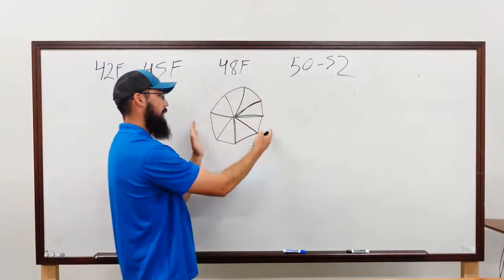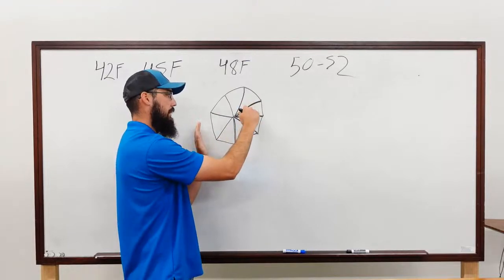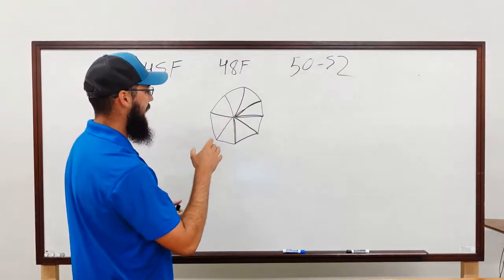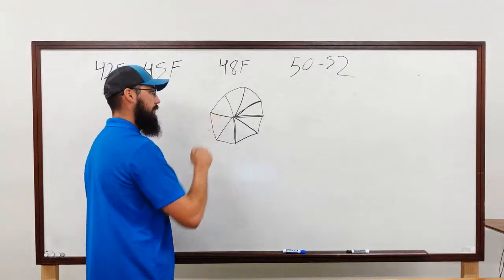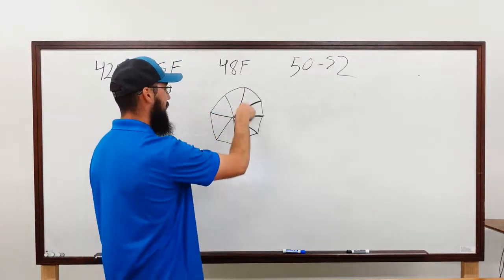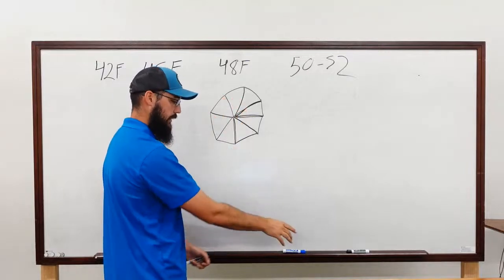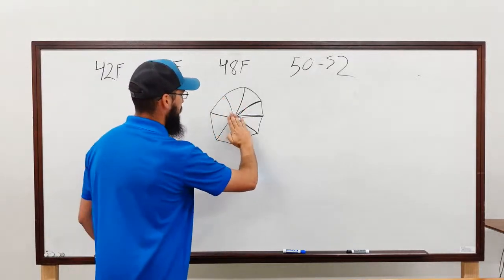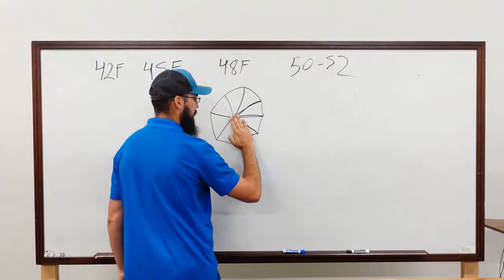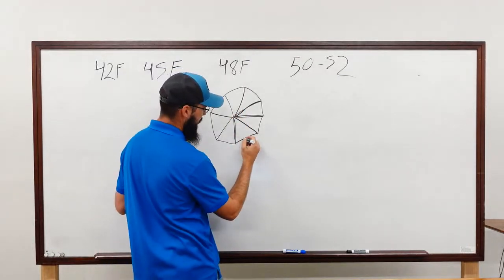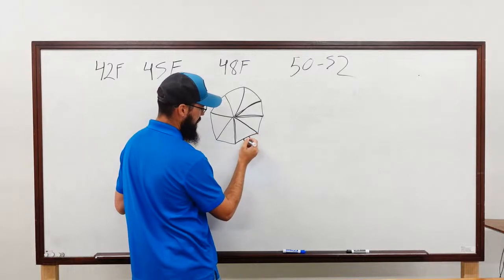All right, so sorry, in case you couldn't see, this is my inlet guide vanes. This would be a front shot looking directly at it if you're staring into the nose cone of a centrifugal compressor. Directly behind this would be the inlet cone of your impeller. And these are just paddles. These paddles just pivot and rotate on hinges, and they'll have just a little bearing hinge.